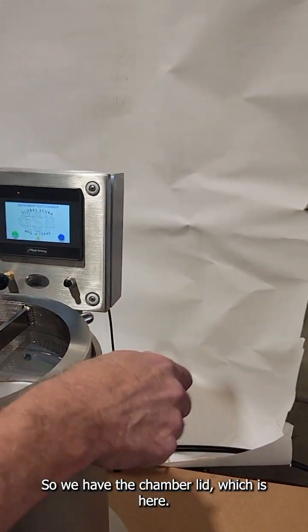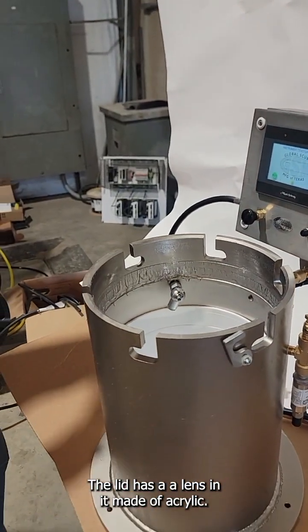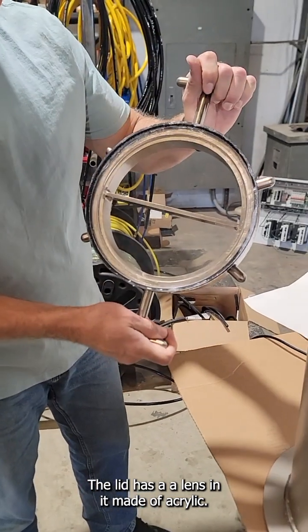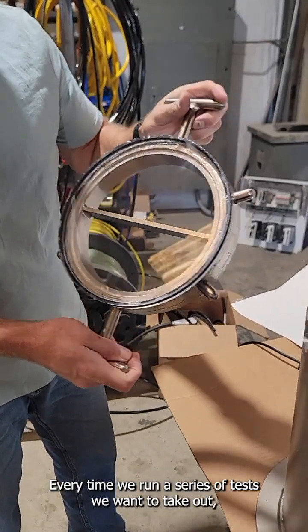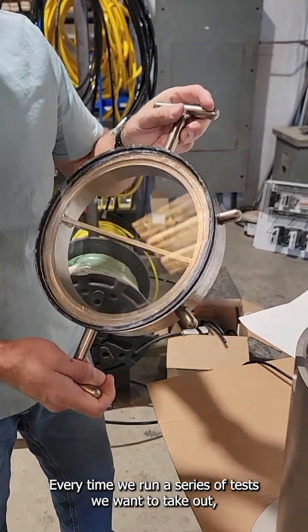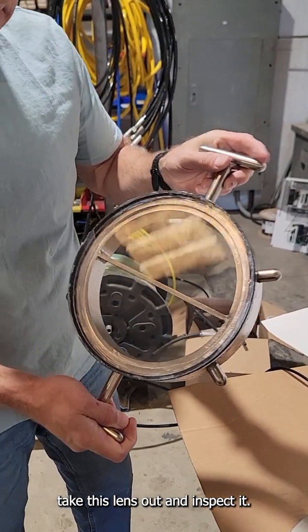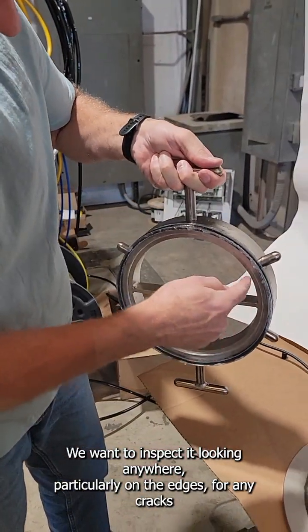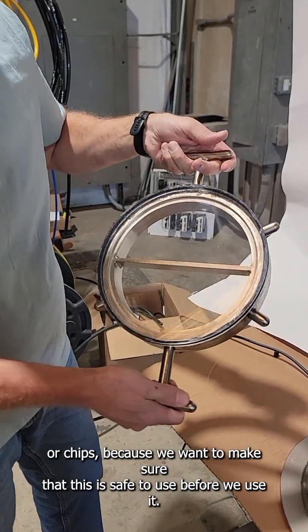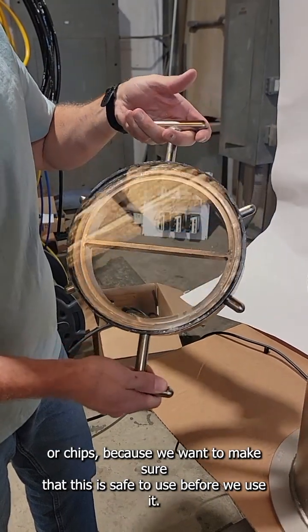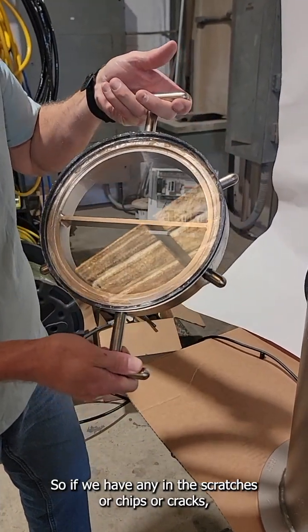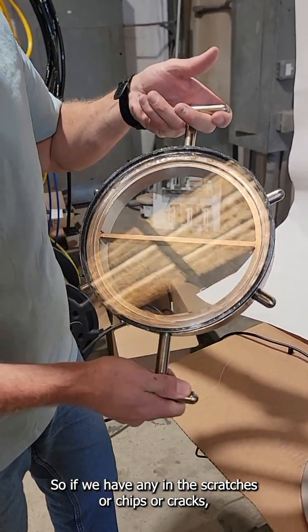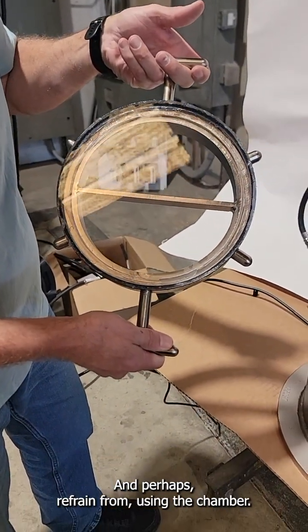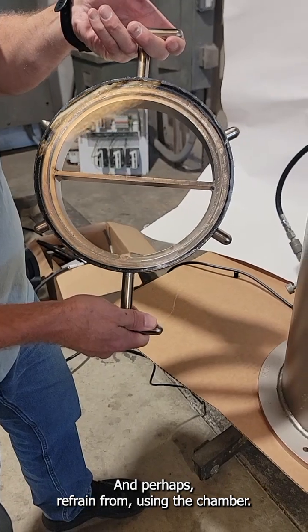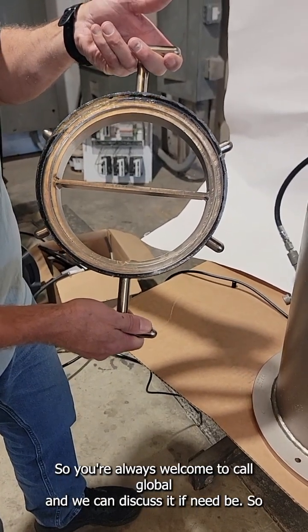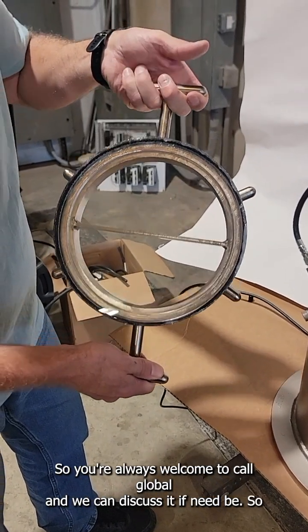So we have the chamber lid, which is here. The lid has a lens in it made of acrylic. Every time we run a series of tests, we want to take this lens out and inspect it. We want to inspect it, particularly on the edges, for any cracks or chips, because we want to make sure that this is safe to use before we use it. If we have any scratches or chips or cracks, that's something we need to take note of and perhaps refrain from using the chamber. You're always welcome to call Global and we can discuss it if need be.